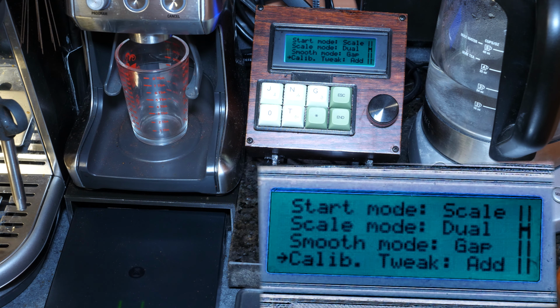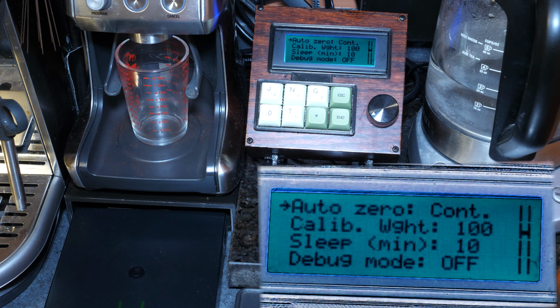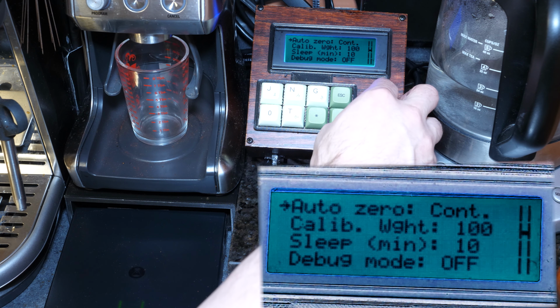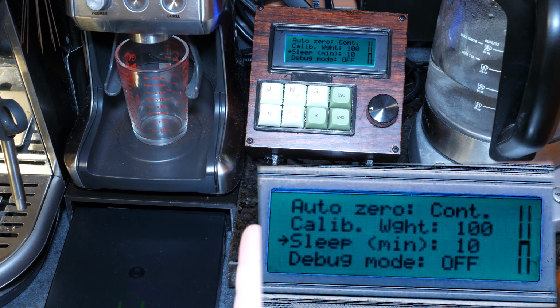You've got some options on how to calibrate the scales at startup. Normally you calibrate them once in a while with a known weight, and then when it starts up it knows the weight should be 0, so it might do some minor tweaking in the beginning. You can choose how that's done. You can also choose how to auto-zero, a related thing to calibrating the scale. When it's 0, you can tell it to constantly monitor the weight, and when it thinks nothing's on it, make sure that's calibrated to 0. You can tell it the sleep time, how long before it automatically goes to sleep and wakes up.